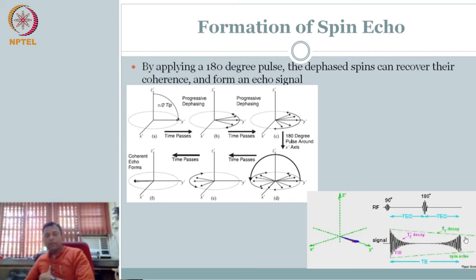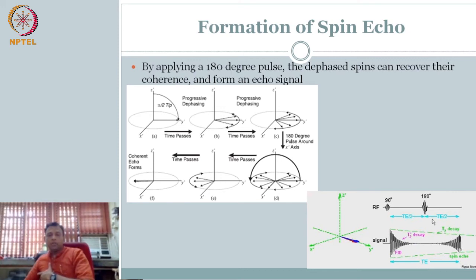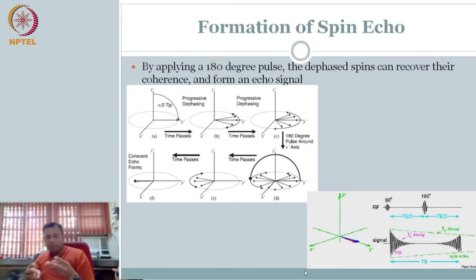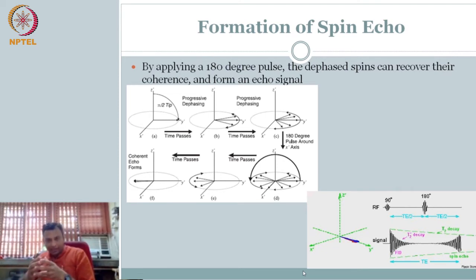You get an echo of the signal, so there are timings involved — this is the time to echo (TE). T2 relaxation times are material properties. But notice the time to echo is under your control — you know when you want to apply the excitation pulse, so you are applying the time to echo. This timing is also under your control. The whole beauty of MRI is you have multiple parameters inherent to material property, and you can manipulate what you want to get of the material by changing the sequence in which you apply the RF excitation pulse.